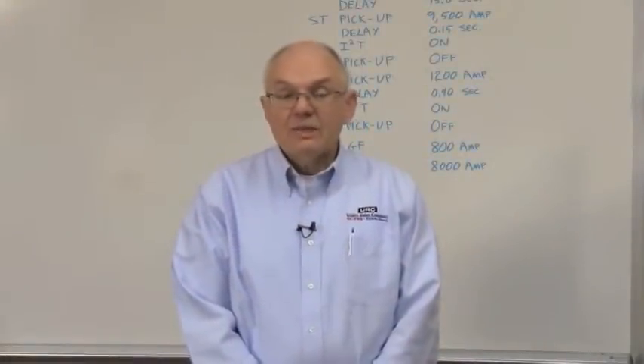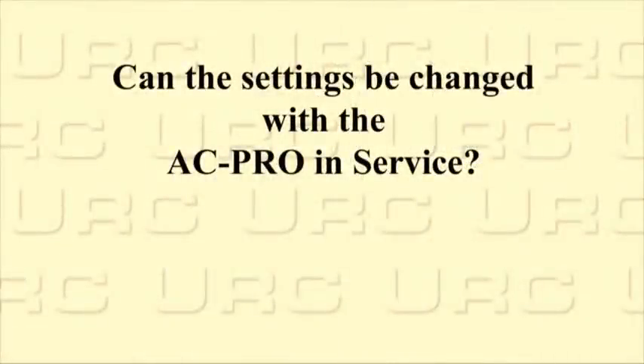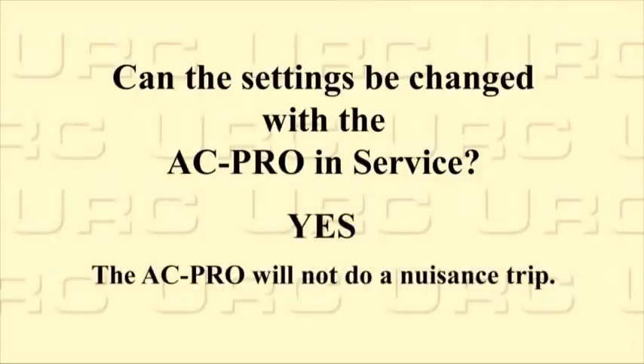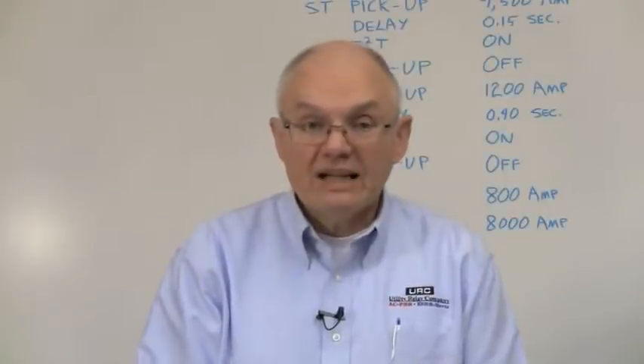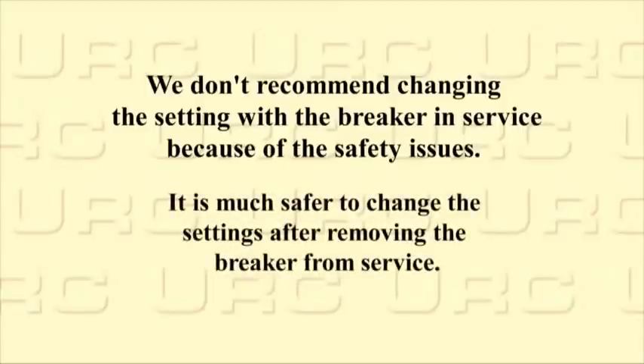If a coordination study is not available, then the alternative is to match the settings of the protective device being replaced. The other commonly asked question is: can the ACPro settings be changed with the trip unit in service? The answer is yes. The ACPro will not do a nuisance trip. Protection is provided during the whole process except for about a half a second at the very end when the ACPro recalculates all its internal constants. However, we don't recommend changing settings with the breaker in service because of the safety issues. It is much safer to change the settings after removing the breaker from service.